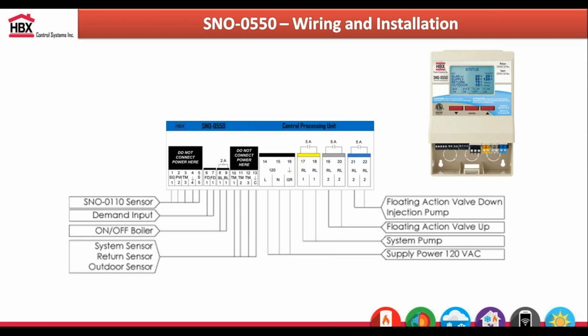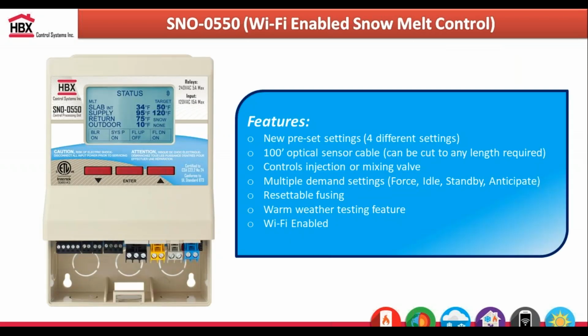You also have the option to add an external demand input. If you wanted to put an on-off switch or a momentary switch in the garage to put the controller automatically into melt mode, you can hook up that switch to pins 6 and 7. We can send an on-off signal on pins 8 and 9. You also need to connect the system and return sensors as well as an outdoor sensor to the controller. We can also control a mixing device on the Snow 550, so we can control an injection pump or a 3-way mixing valve, as well as the main system pump circulator.